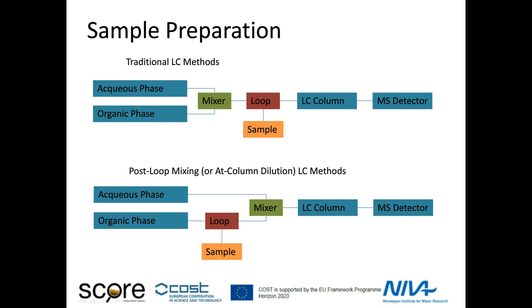It is extremely efficient. I now inject between 50 and 100 microliters of 100% organic straight onto aqueous LC and get incredibly sharp peaks, which obviously increases sensitivity.